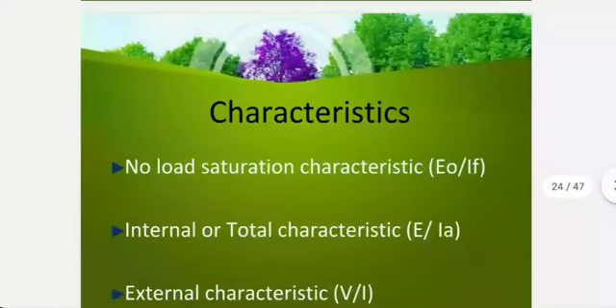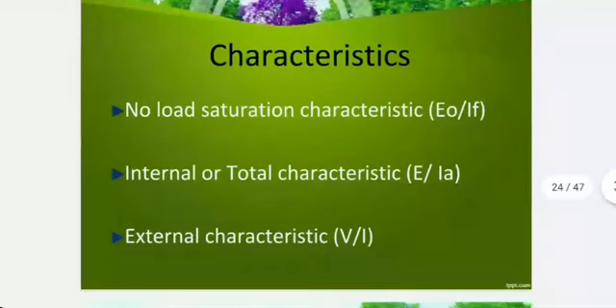Now, as a generator, what are the things that matter to the rest of the world? It is easy to think that the electromagnets will produce more and more magnetic flux as you increase the current going into the field windings. In practice, it doesn't happen, because the materials used for the poles saturate. After a certain value of field current, even if you put more current in, the flux would hardly change. Saturation comes in.